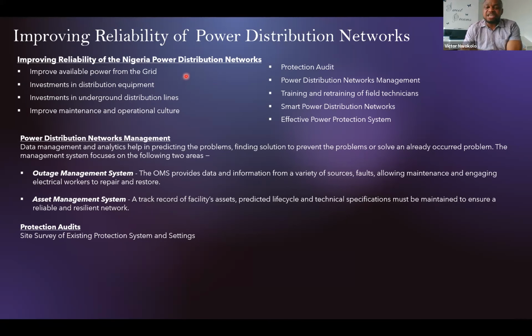An example of them is making sure you carry out protection audits. Like I stated, if the protection systems on those substations are regularly inspected, maybe through site surveys, you will pick up insufficient power protection. And as a result, you anticipate the unreliability of your protection system in the case of a fault. And if you have proper power distribution network management. So 2 things we look at there. One of them is the outage management system. So this provides data and information from various sources about faults, allowing maintenance engagement of workers.